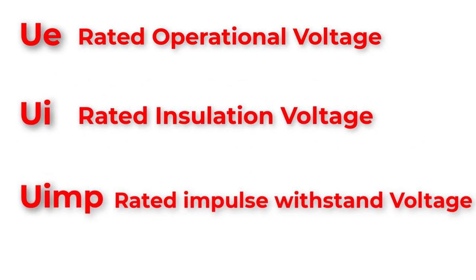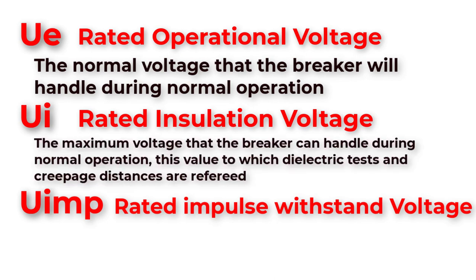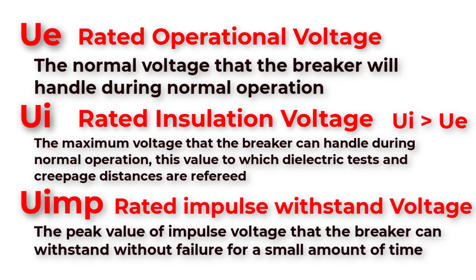The rated operational voltage is the normal voltage that the breaker will handle during normal operation. The rated insulation voltage (Ui) is the maximum voltage that the breaker can handle; the operational voltage shall not exceed this value, and it is the voltage to which dielectric tests and creepage distances are referred. The rated impulse withstand voltage (Uimp) is the peak value of voltage that the breaker can withstand without failure for a short amount of time.